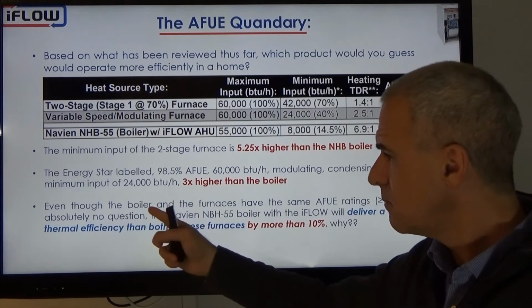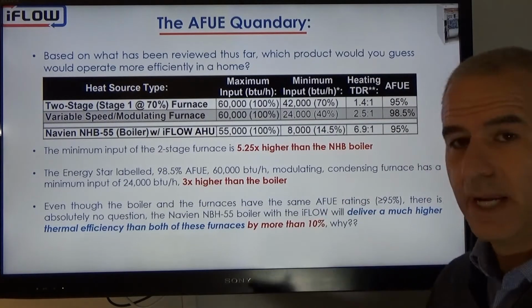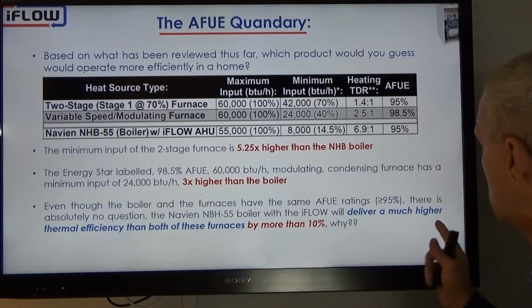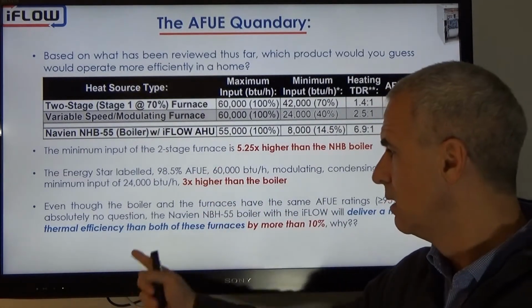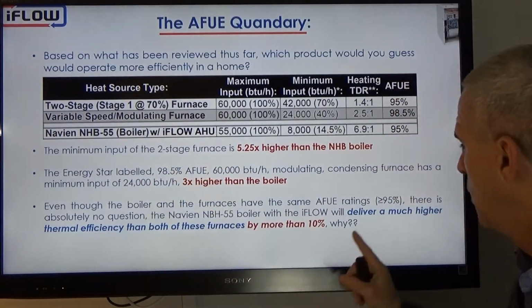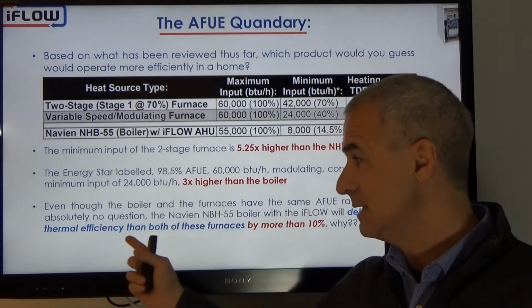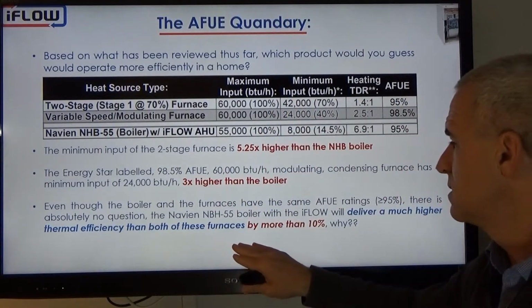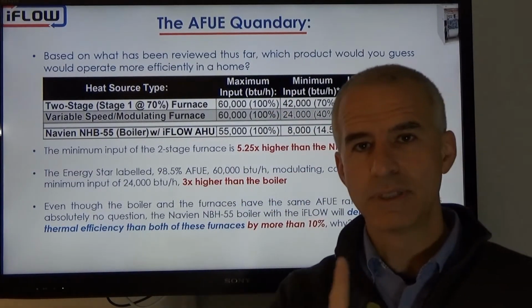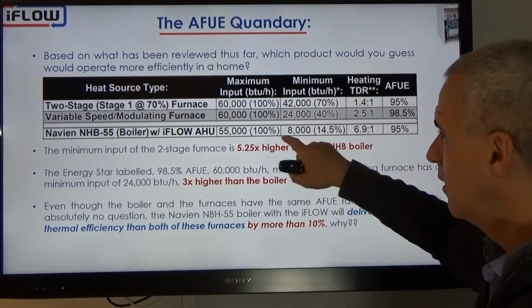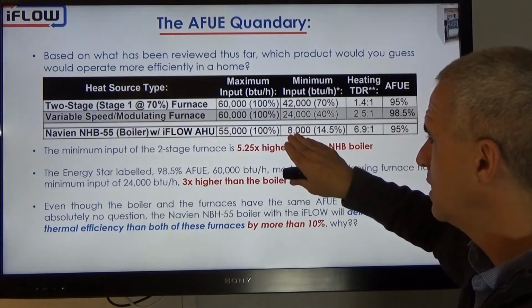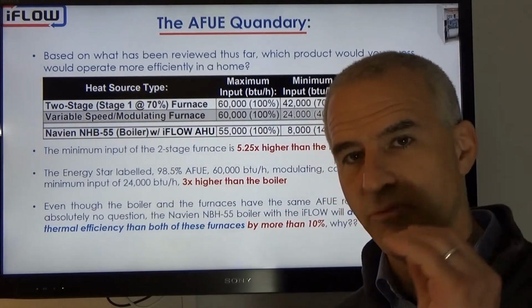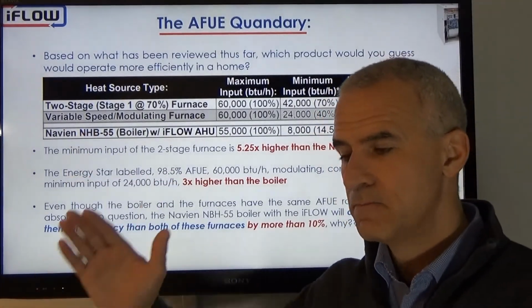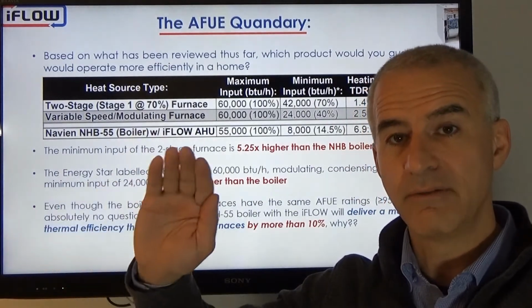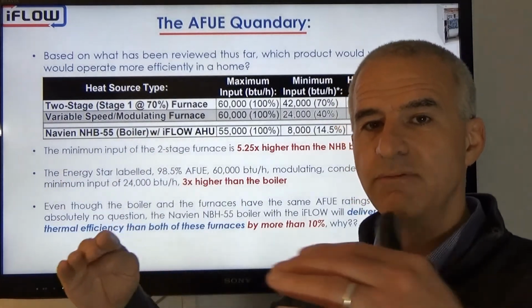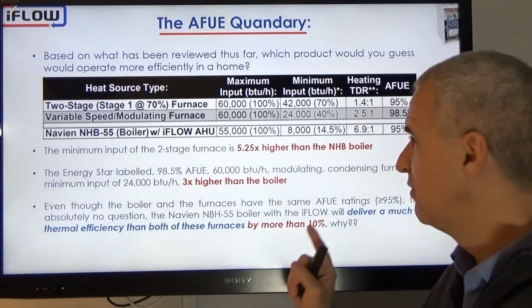So even though the boiler and the furnaces have the same AFUE readings, let's say all above 95%, there is absolutely no question that the Navien NHB with the iFLOW will deliver a much higher thermal efficiency into the house than both of these furnaces by, my estimate, more than 10%. Why? The simple fact that you're going to get all of the gain because of the low modulation rate in September, October, November, into December, and then again in March, coming out of February into March and April, where you can just deliver the heating that's needed and not cycle, your efficiency gains will be huge.